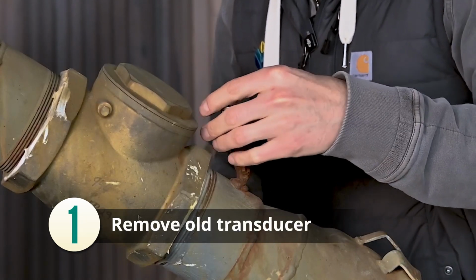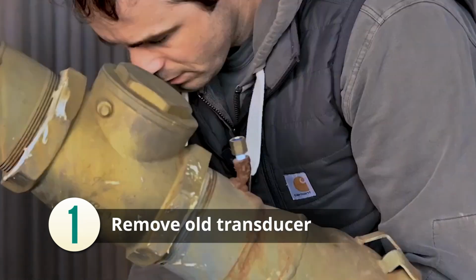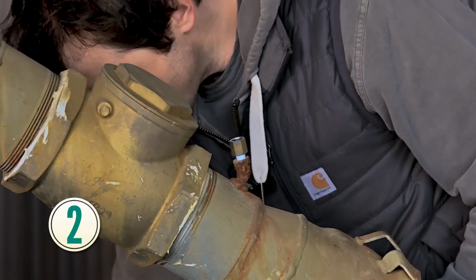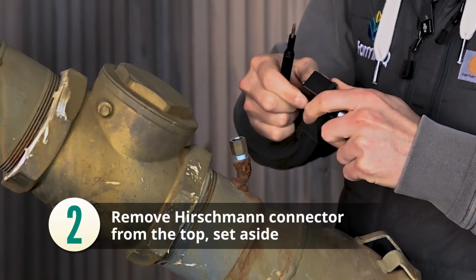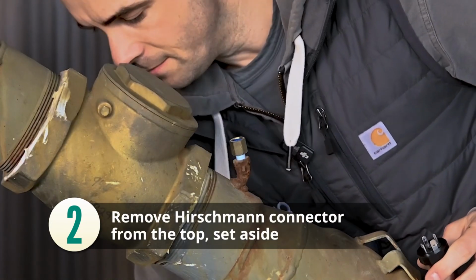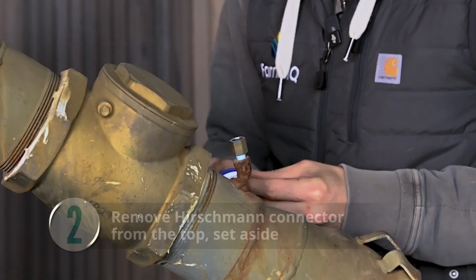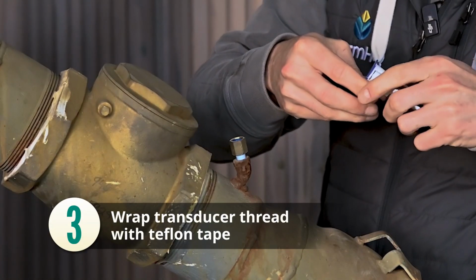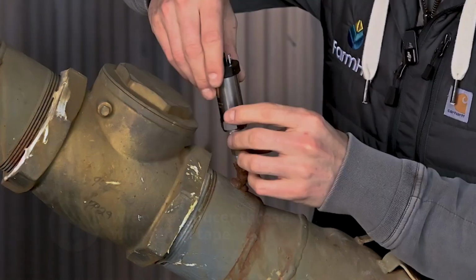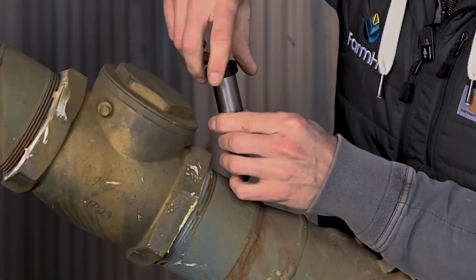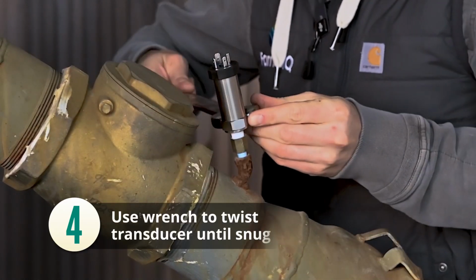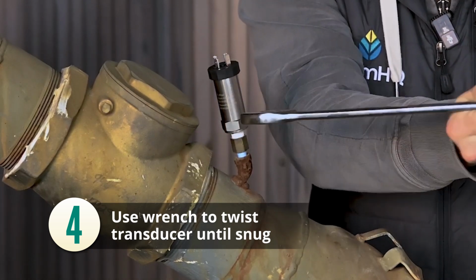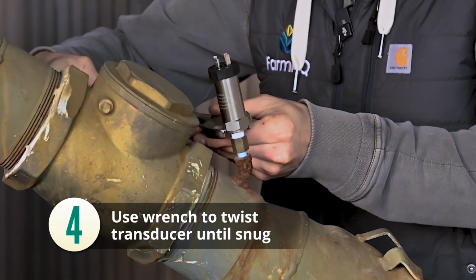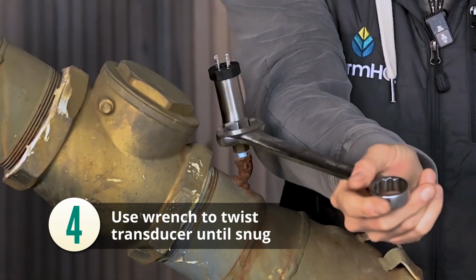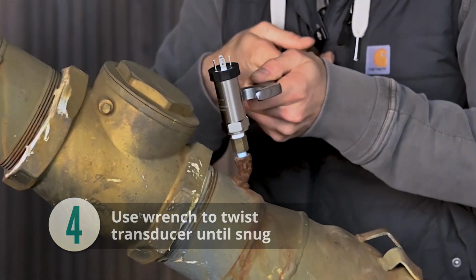Take our channel lock wrench, remove the old bad transducer. One's gone. Take our new transducer here. You can just go ahead and remove the Hirschmann connector from the top, save that for later. Now I'm going to take some Teflon tape and just give it a few wraps. Then go ahead and thread that new transducer on. This takes a 27mm wrench. We'll go ahead and just give that a few rotations until it fits snugly. There we go, I'm happy with that.